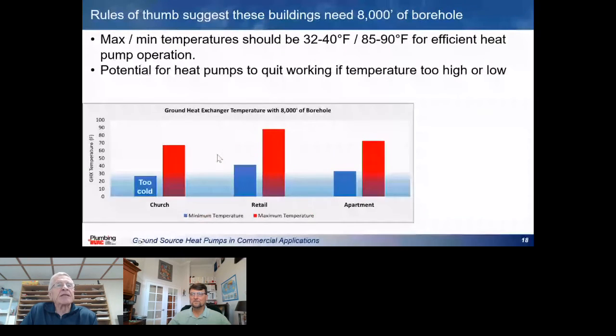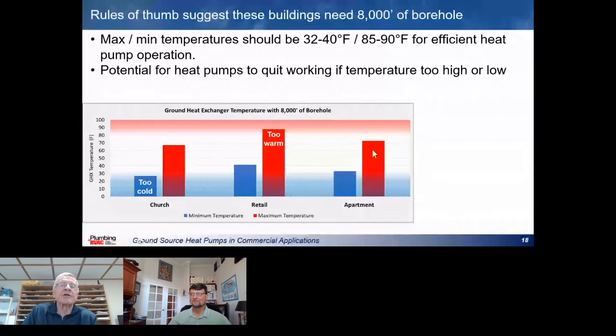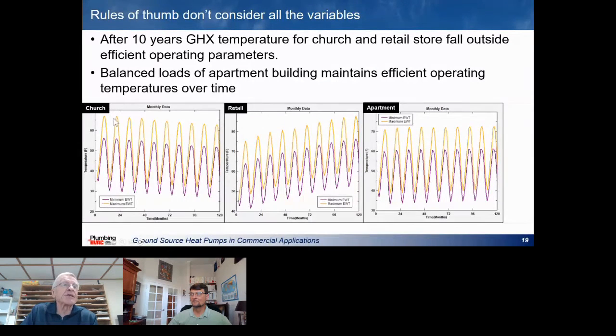So what that means for what the temperatures of the ground loop are going to do over the years: this one's eventually going to get too cold because you're extracting more heat from the ground than you're putting in. This one's going to do exactly the opposite. It's going to get too warm. This one's going to be just right, well within the good, efficient operating ranges of that heat pump. Over time, over 10 years, this one's going to drop in temperature. This one's going to increase in temperature to the point where the heat pumps aren't going to operate efficiently. And this last one is going to stay within that same efficient operating range for the life of the building.